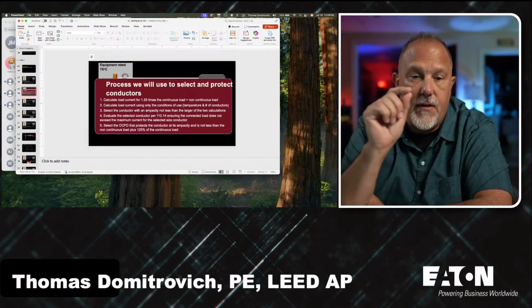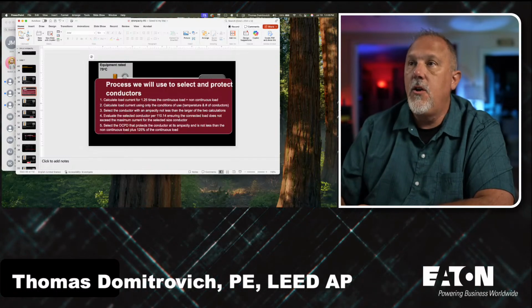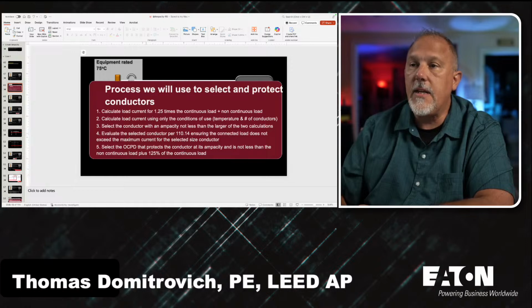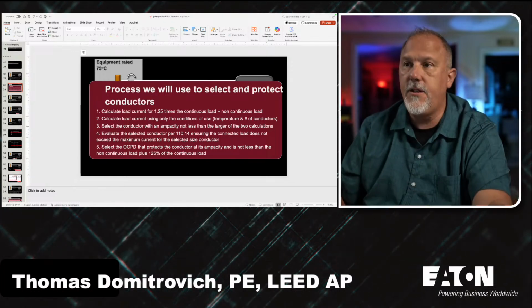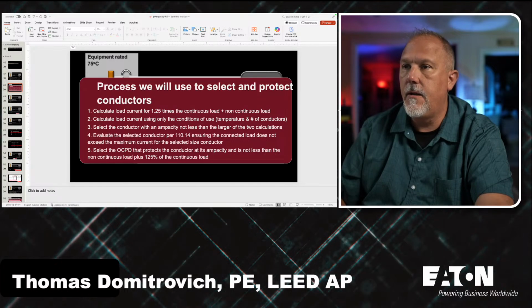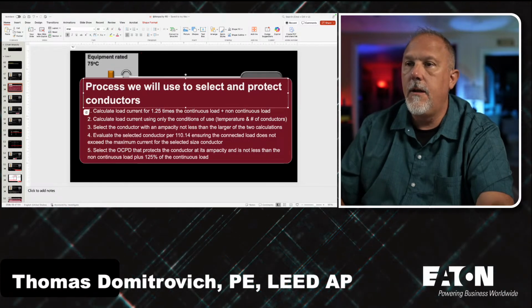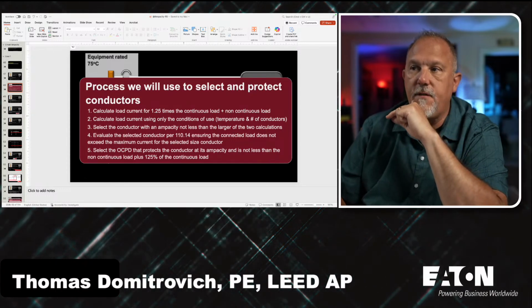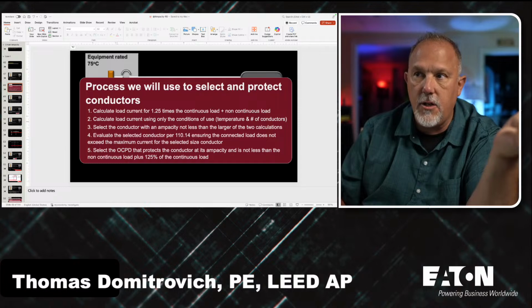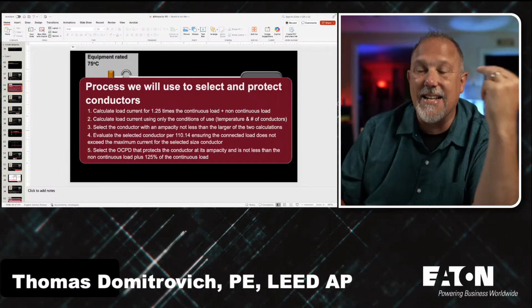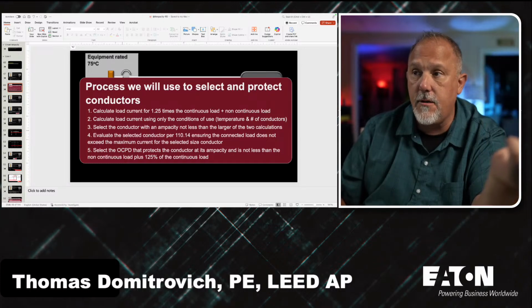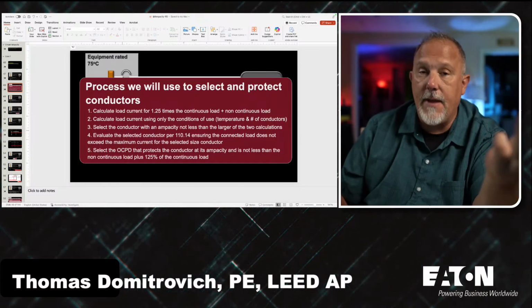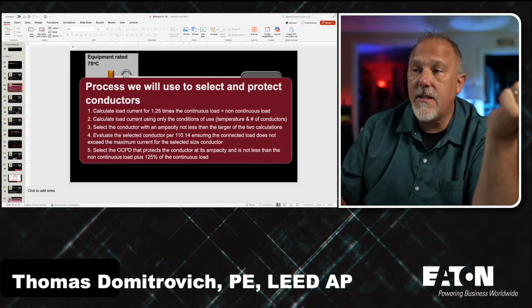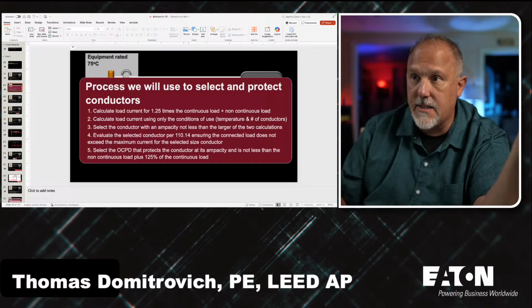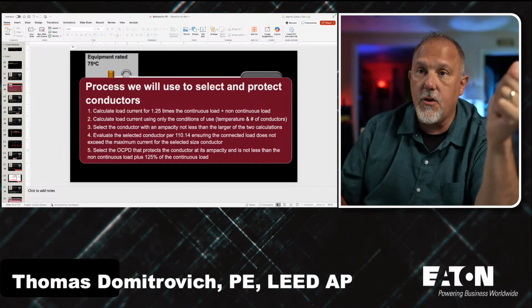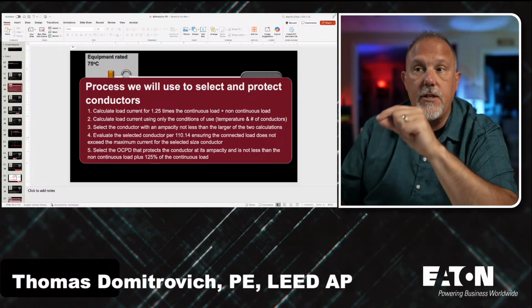We're going to follow these 5 steps. We are going to calculate the current. Calculate the load current for 1.25 times the continuous load plus non-continuous. We're going to calculate the load current using only the conditions of use. We're going to select the larger of the two and pick our conductor that has an ampacity that can handle that larger number. Then we're going to evaluate the selected conductor to 110.14, considering the terminations. And then we're going to select our overcurrent protective device. So that's the process that we're going to use. We're going to stick to it.